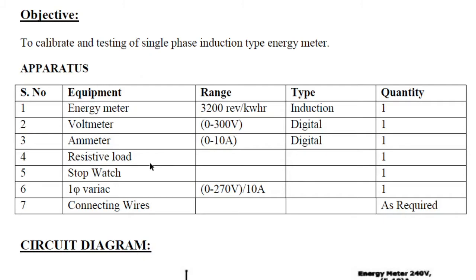We need a resistive load which has rotary switches. We are going to apply this resistive load on the energy meter and observe how the meter reacts. We also need a stopwatch to count how much time it takes to revolve 10 times for each load, and a single-phase variac — a variable voltage auto transformer of 0 to 270 volts, 10 amps range — and connecting wires as required.